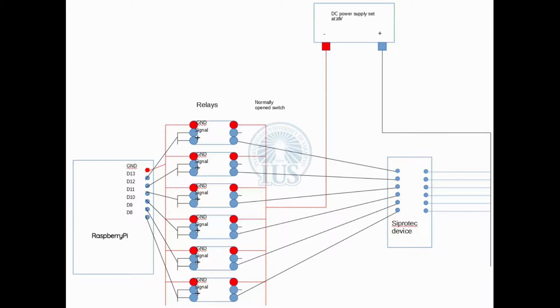When we press, for example, to simulate a critical temperature increase, the Raspberry Pi sends a signal to the relays, and the relays trip on the output side. As you can see, it says normally open circuit. The output side of the relays is open, so no current can flow. When the Raspberry Pi trips the relays, they close and allow current to flow. The Siprotec device then receives the 20 volt signals, and that's like a warning to Siprotec: oh, look, something happened there, I need to take action. That's how the Siprotec device knows when to trip. And there's the same logic for the other 5 relays.